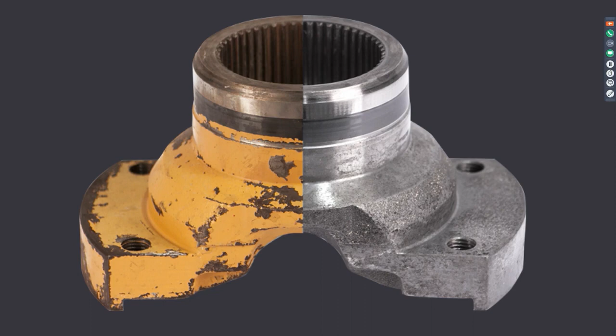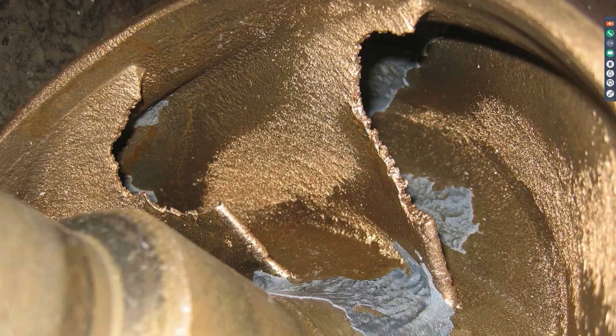So at some point we have to form a balance between how much cavitation energy is too much or not enough, because we have a heavy load to balance in sterile processing to get those sets back up to the OR. Here's an impeller that shows drastic abuse through cavitation as it spins through water. So cavitation is good, and it can be a bad thing. Let's look at one of these mysterious, very highly powerful bubbles. We'll step through this. As that negative pressure occurs, like we saw with the mantis shrimp, a funnel begins to appear inside the bubble. The bubble begins to turn inside out through what we call a jet in this area right here. And this bubble is actually imploding in on itself, creating a pressure that can help to remove bioburden off of surgical instruments.